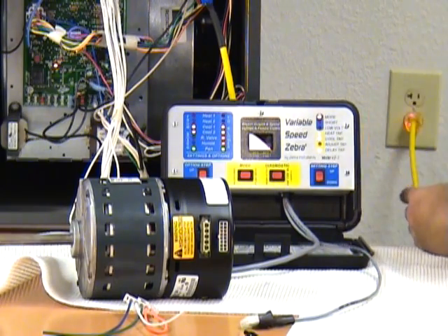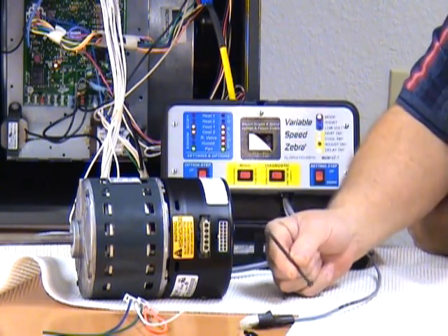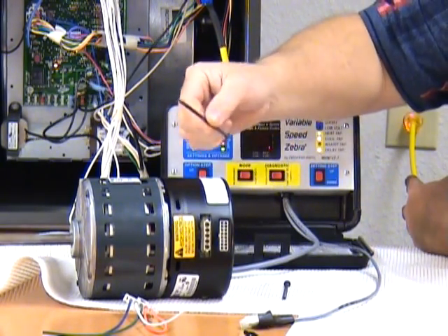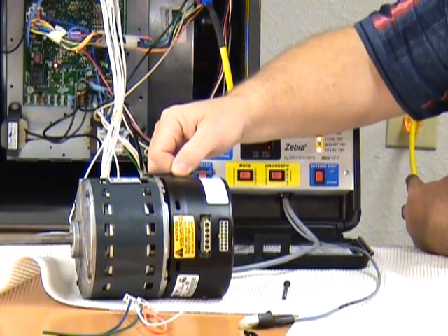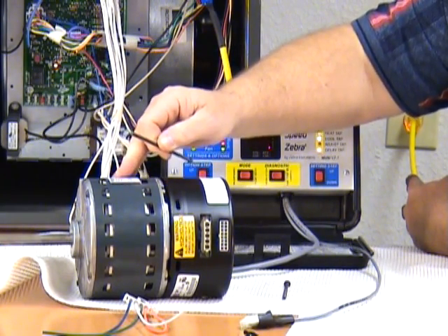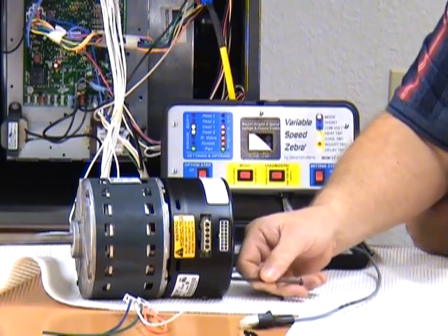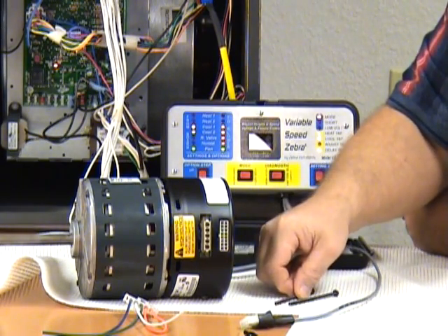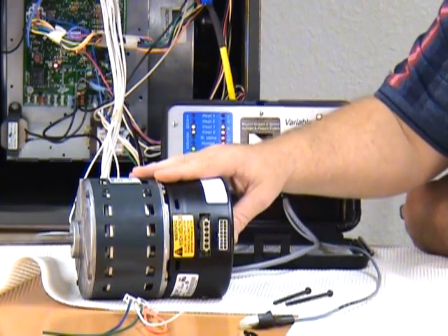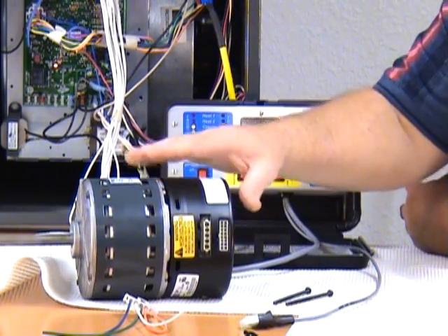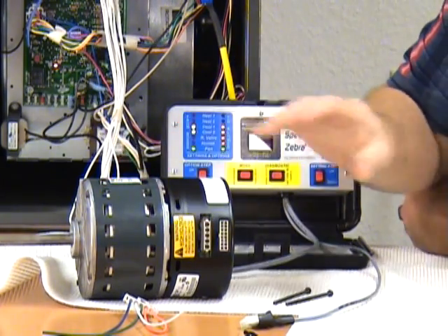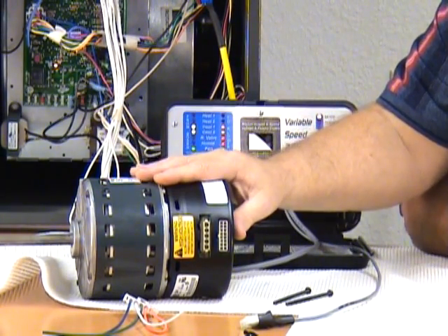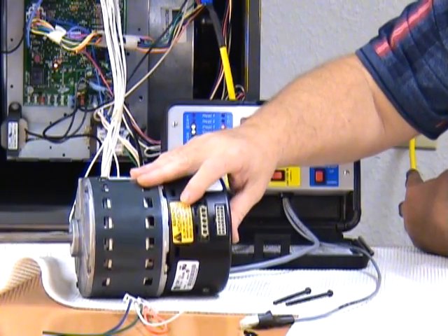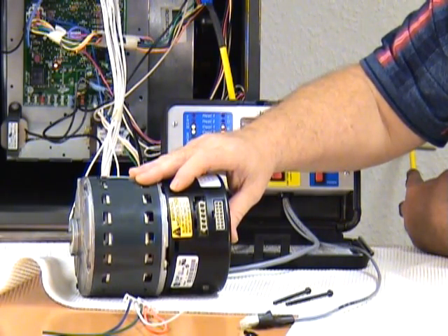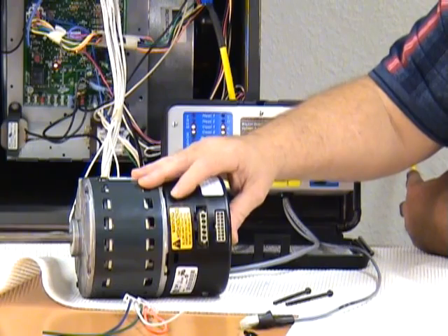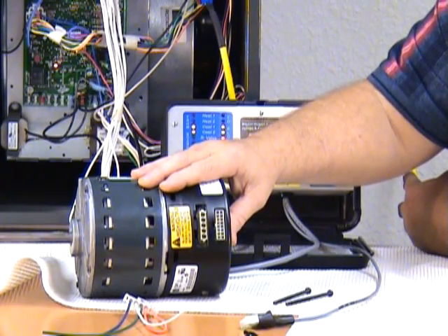There are 2 bolts that I've already removed that hold this module to the winding section of the motor. Don't remove either one of those 2 bolts until you've waited 5 full minutes after you've removed the power connector from the motor. This motor has large capacitors. See the warning high voltage thing says allow 5 minutes after disconnecting before opening motor. That's a real serious thing.